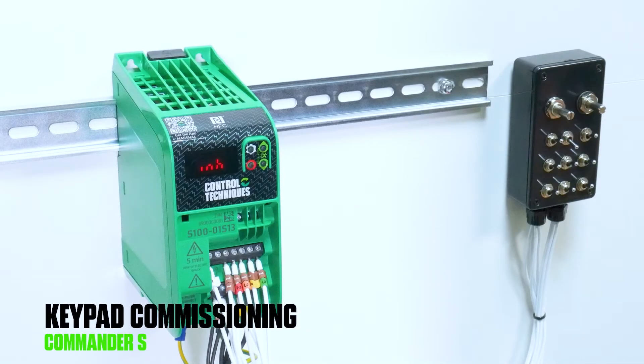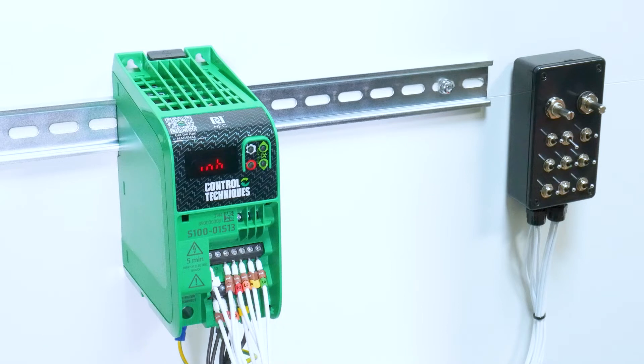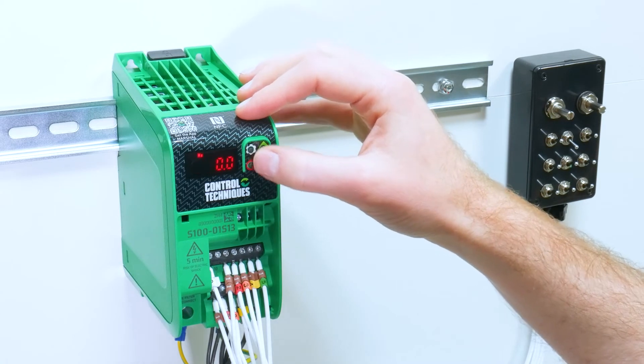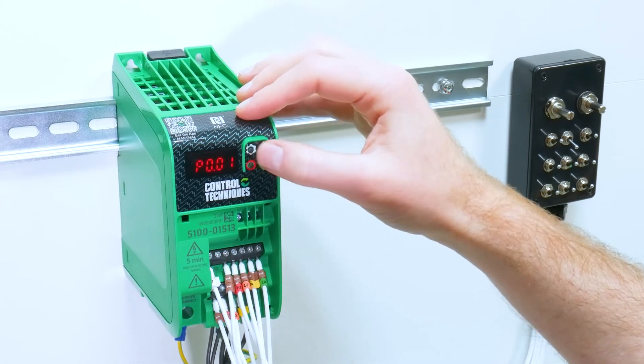When powered up, the drive will display INH, which is for inhibit. Pressing the settings key will go into the parameters. Parameter one is our minimum frequency limit. Parameter two is our maximum frequency limit.